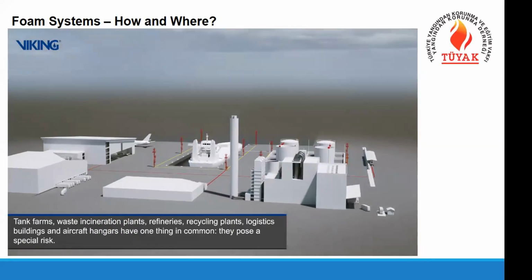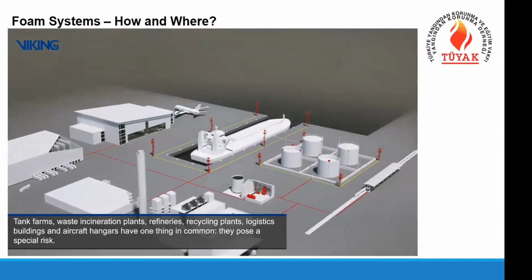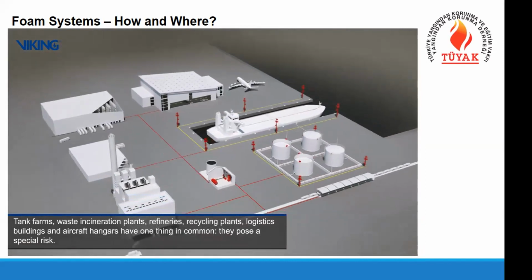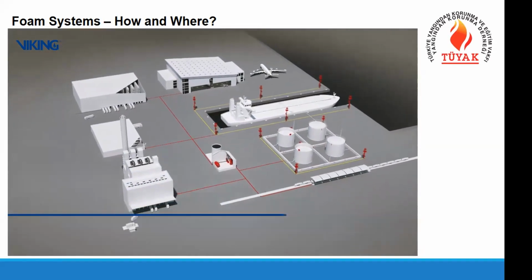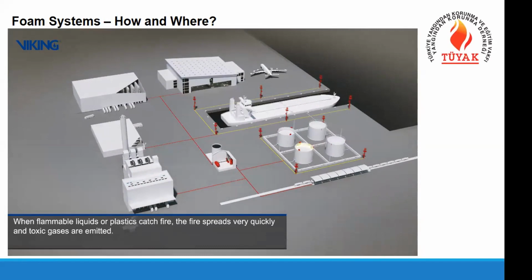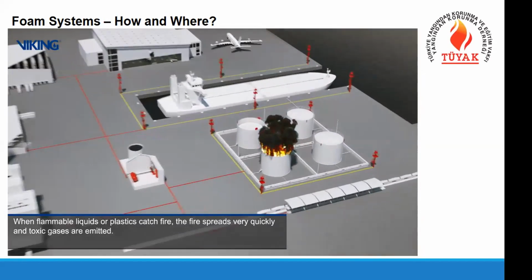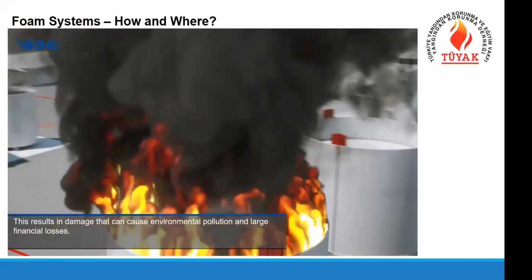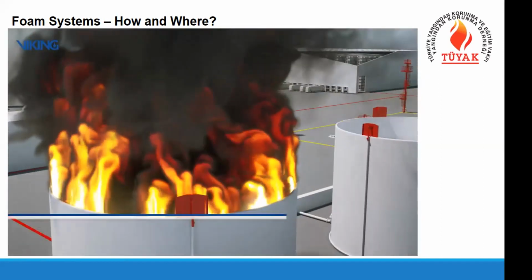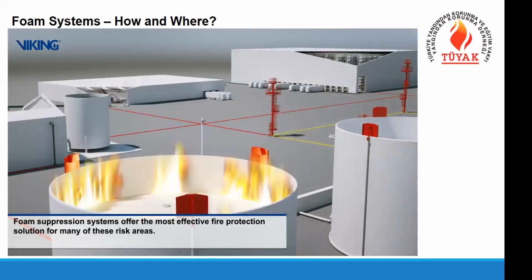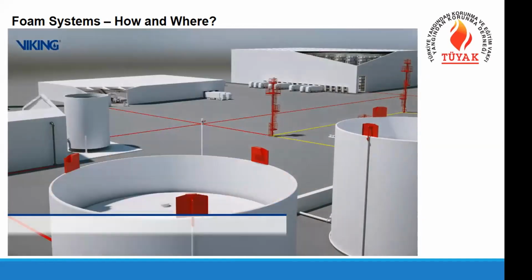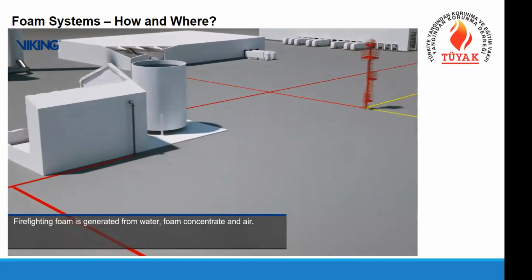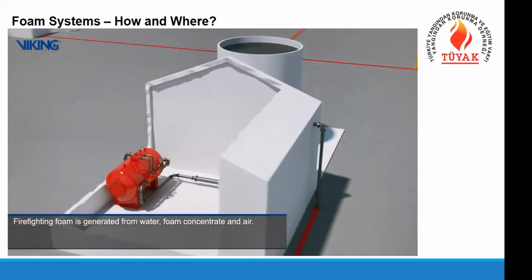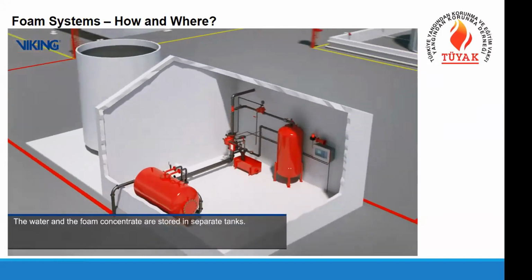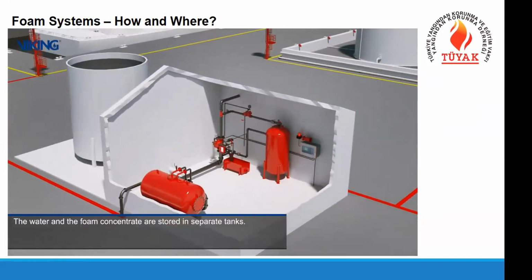So where do we use these foam systems? Typically in almost all industrial plants that have flammable and combustible liquids like diesels, paints, solvents, and other chemical fluids that can be flammable and combustible. When you have a fuel tank and it's burning, it's very hard to control its fire. So we have a high performance system with the foam system.